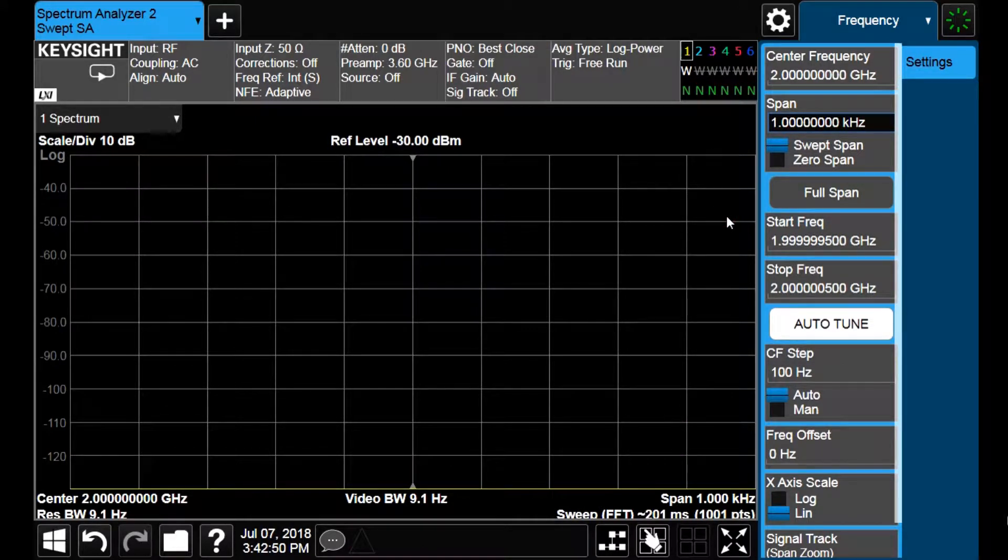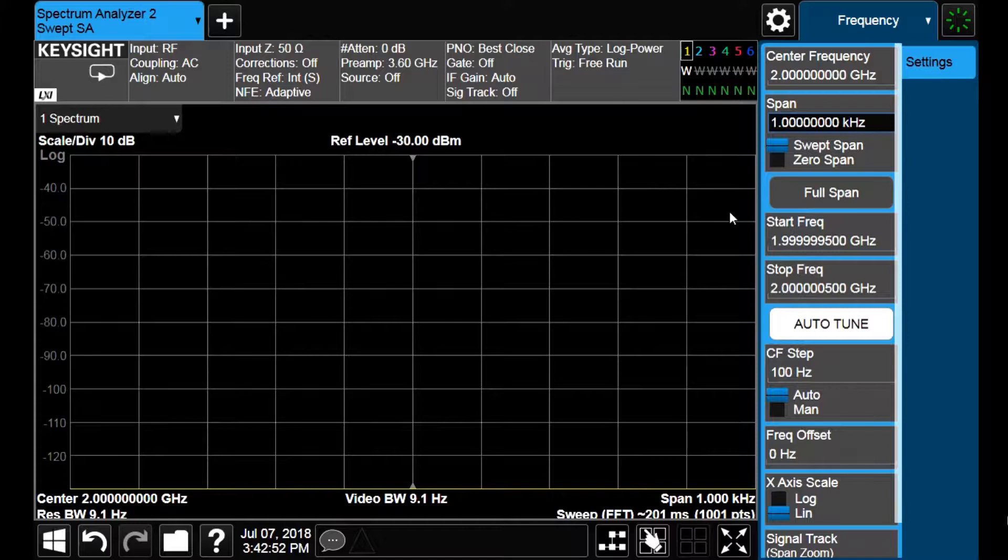We go to the frequency menu and choose a center frequency of 2 GHz and a span of 1 kHz. Doing this, both bandwidths are automatically reduced and the noise floor level drops well below minus 130 dBm. This level is usually called displayed average noise level.